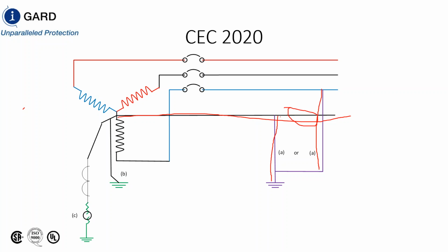You also have to monitor the integrity of the resistor here. If the resistor becomes open circuited, or if the connection of the transformer to the resistor becomes short circuited, that must be detected. So we basically have a relay that does all this, and it's called the Sigma relay.